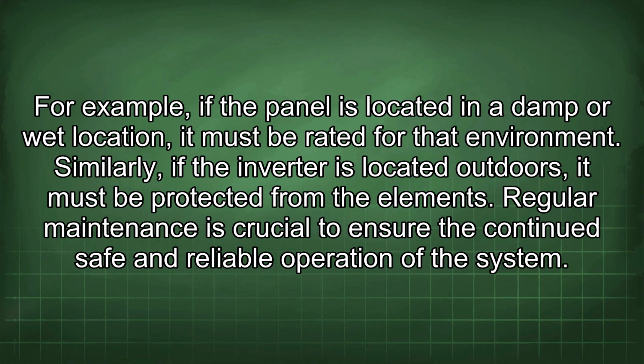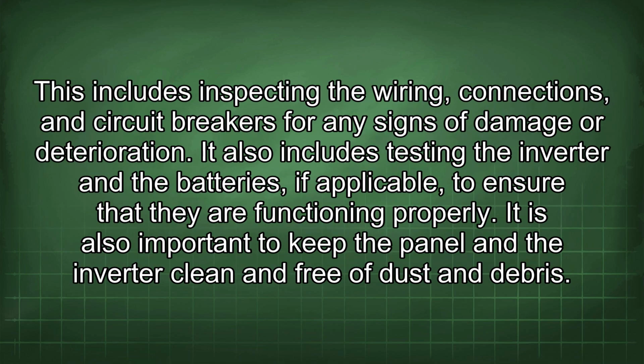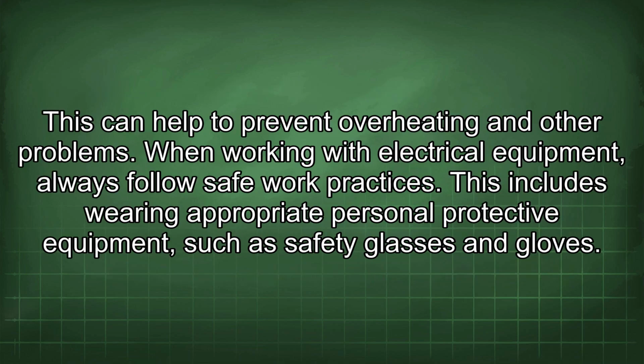Regular maintenance is crucial to ensure the continued safe and reliable operation of the system. This includes inspecting the wiring, connections, and circuit breakers for any signs of damage or deterioration. It also includes testing the inverter and the batteries, if applicable, to ensure that they are functioning properly. It is also important to keep the panel and the inverter clean and free of dust and debris. This can help to prevent overheating and other problems.